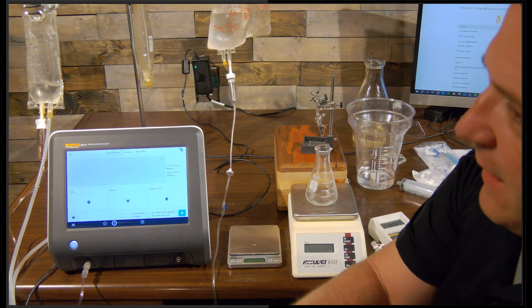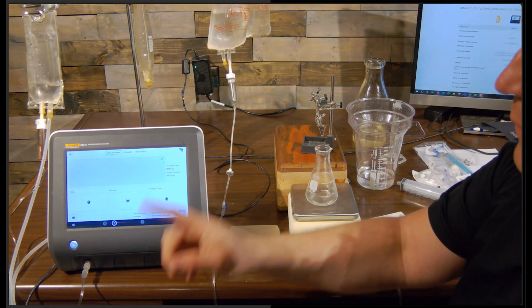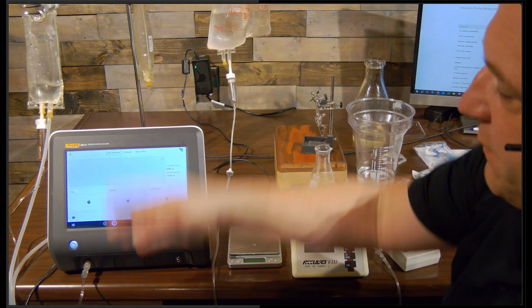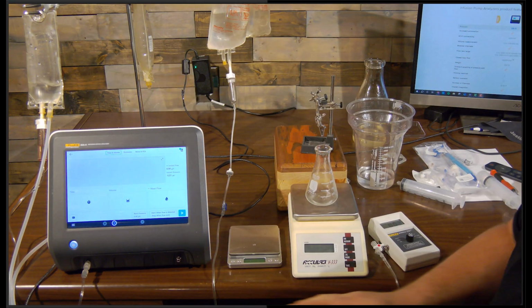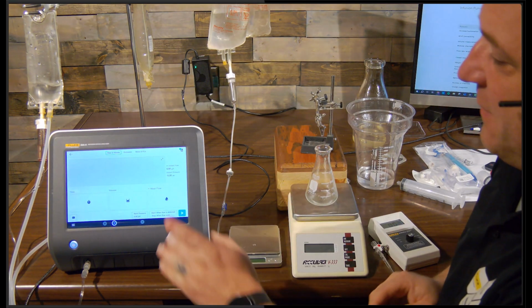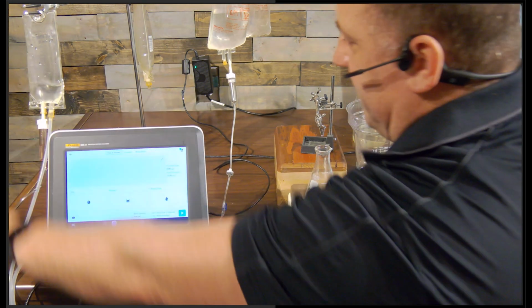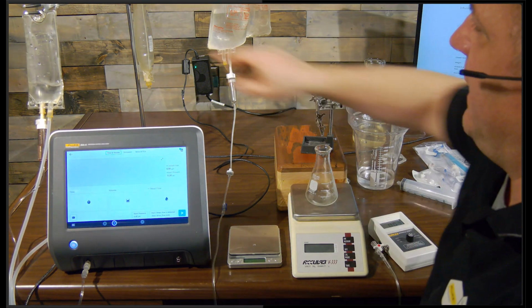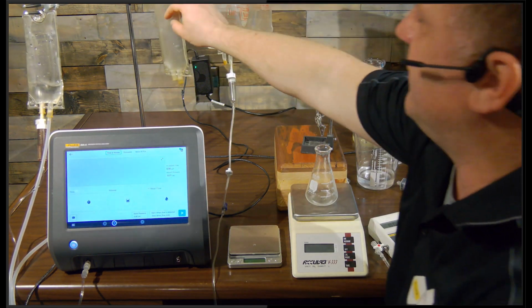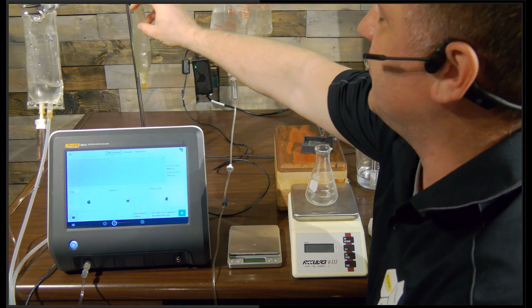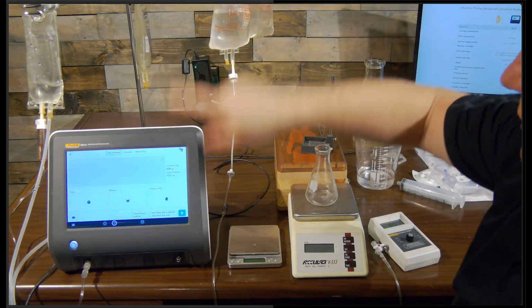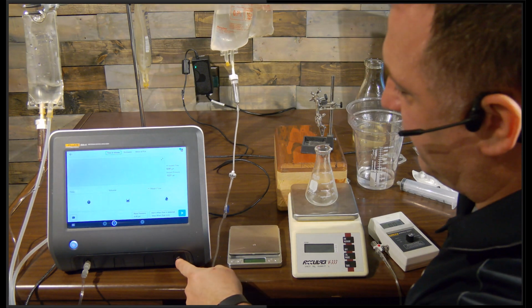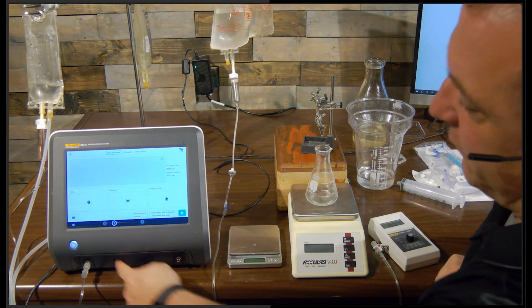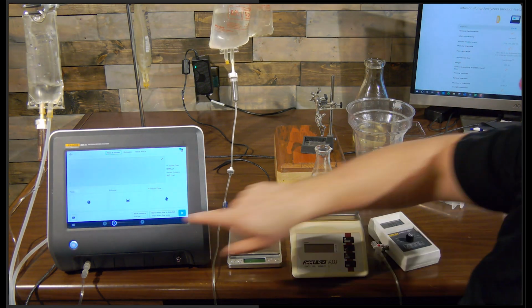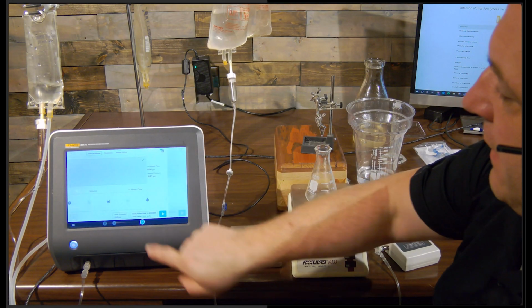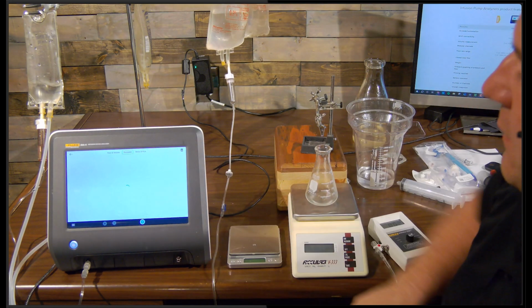Now, for the technicians who really want to follow those manuals and use 2 sets, one for flow and one for occlusion, this is easy enough. I can use one bag here for flow, and then I take a second bag, another one of these little bags, set it up without my calibrated flow tubing set, run it down here and put it into channel 2, or in this case it's channel 4, but my second channel way over here. And I do 1 for flow, and I come over to 4 and hit this for occlusion.